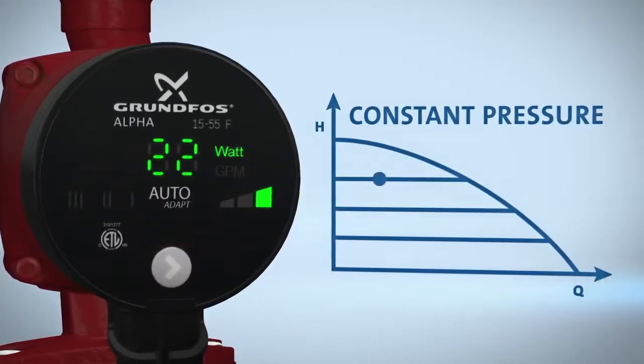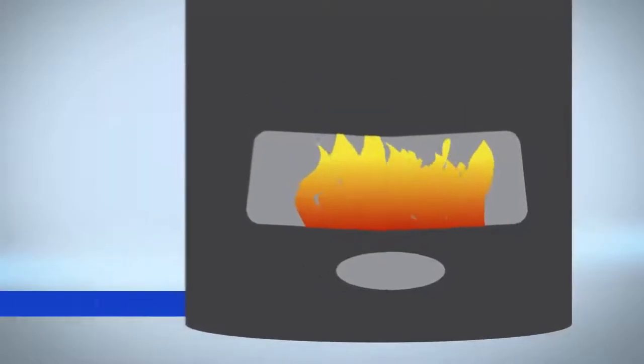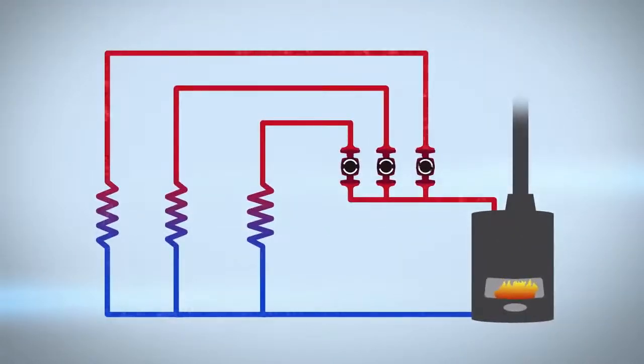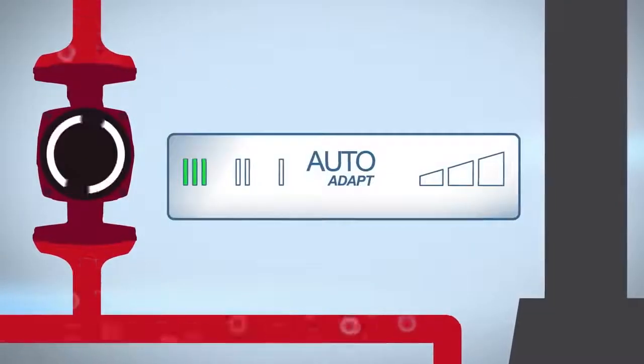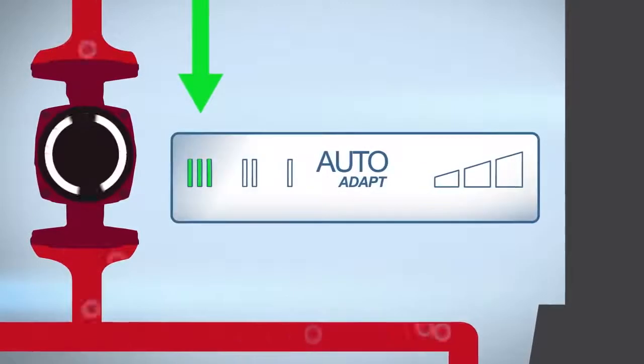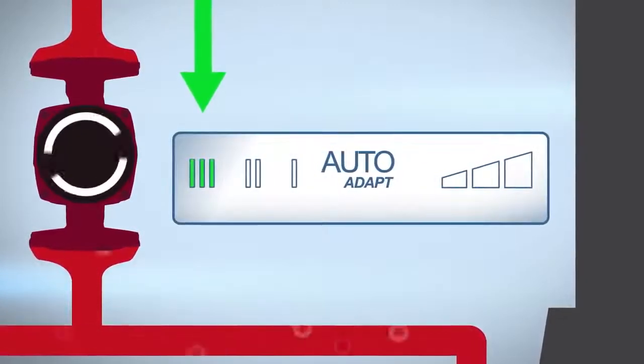Before setting the pump to auto-adapt, ensure the line is clear of any air pockets, also known as purging the pump. To do this, place the pump on speed 3 and begin purging the pump. This process should be done to each heating loop individually.